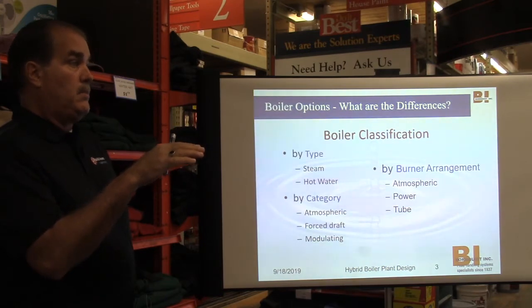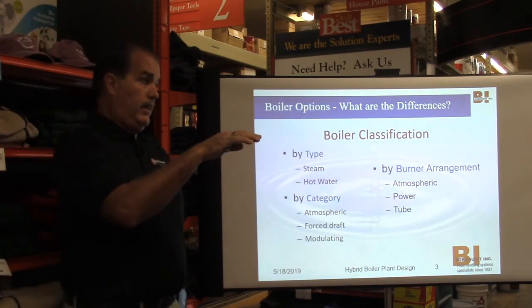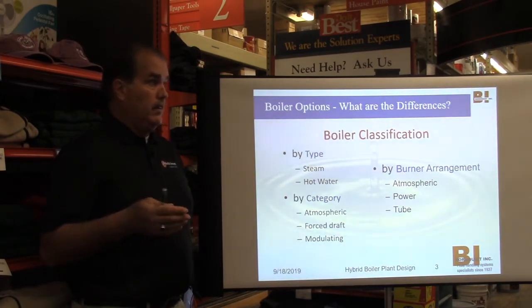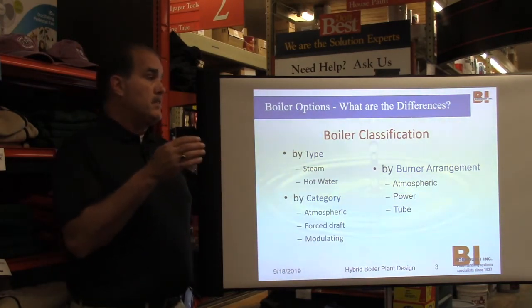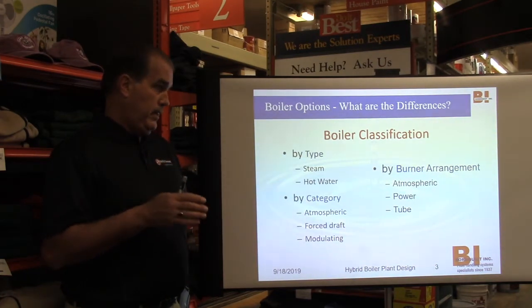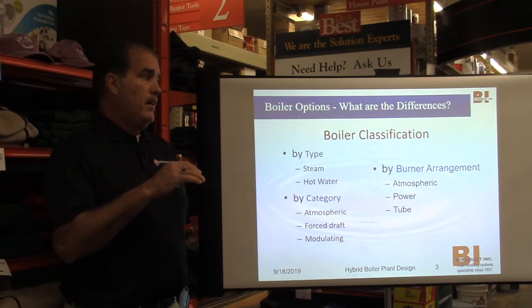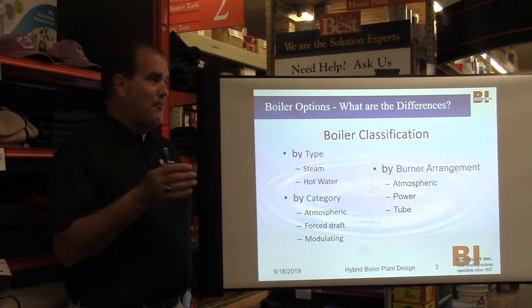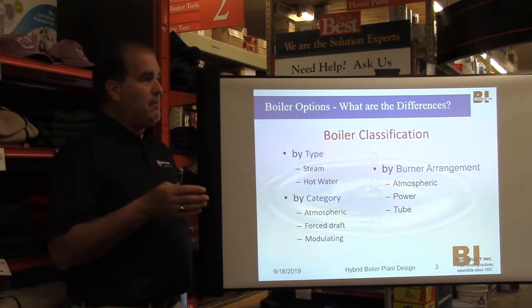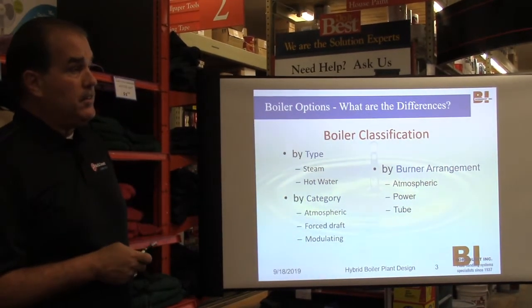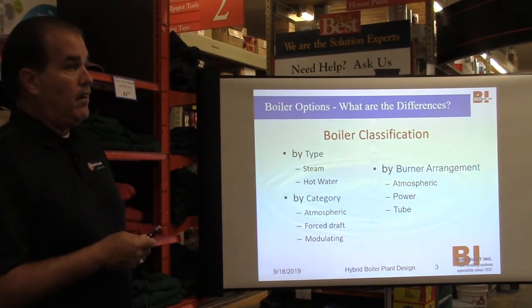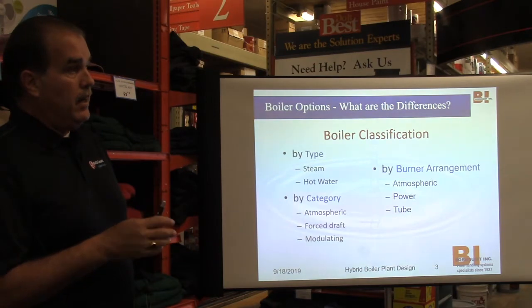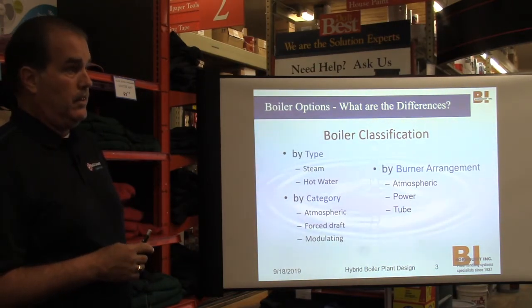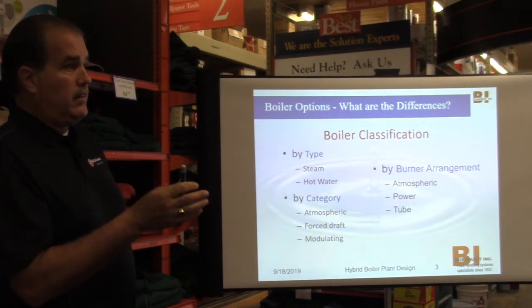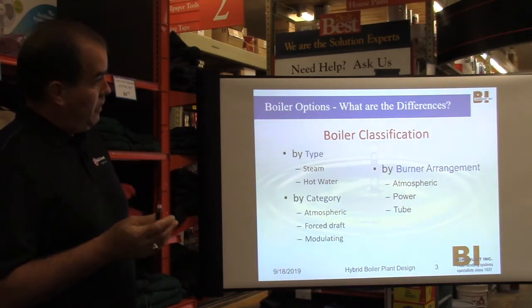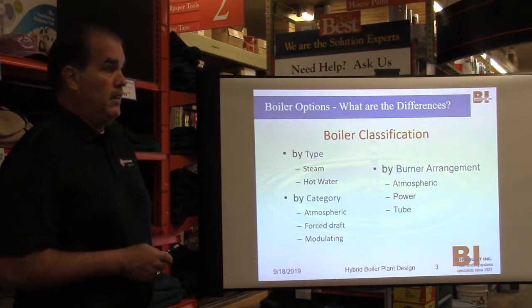Well, that's not what I'm talking about. I'm not saying you can't. In a situation like that, they're probably going to put another steam boiler in. That's the most efficient. If that system is designed well and is maintained well, and it hasn't had a whole lot of people working on it and changing and rearranging the piping and all that, it's fairly efficient. Steam boilers are fairly efficient, even compared to hot water. Hot water boilers are typically a little more efficient, but they're not bad. It's not a huge difference, and so in a situation like that, to convert to hot water is very difficult. So it's done, but it's very rare that it'd be done.